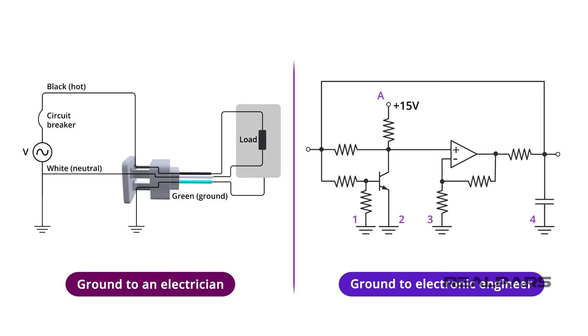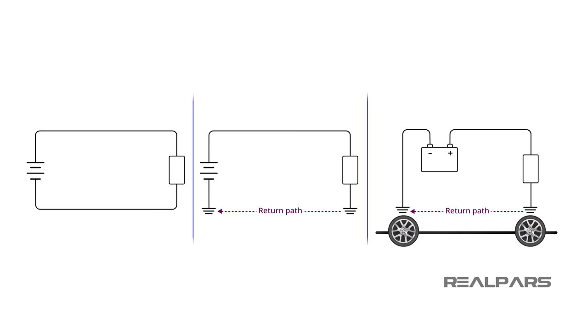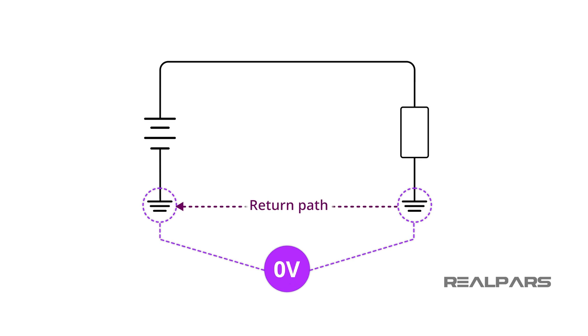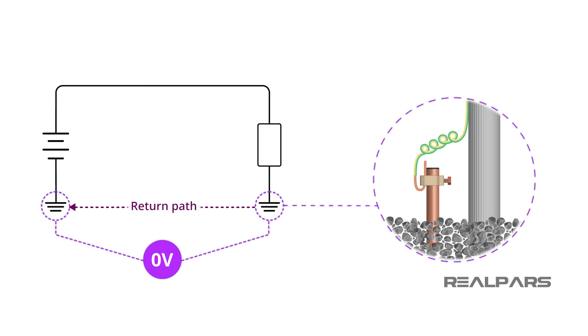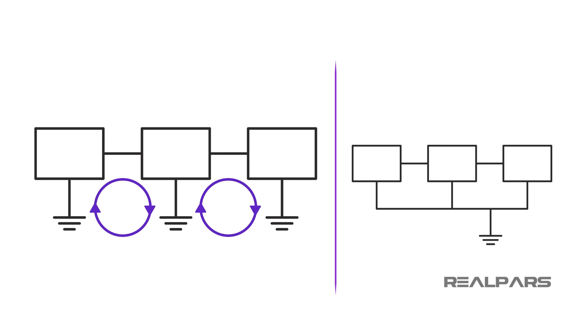Okay, let's review. Quite often, ground means different things to different people. Proper grounding is a critical safety measure in all electrical systems and installations. In many applications, grounding provides a circuit return path. Earth ground is true zero volts. It is the true zero reference for any and every electricity discussion. Earth ground is the reference point in an electrical circuit that is a direct and physical connection to the earth. A ground loop is an unwanted electrical current path that can cause havoc in equipment or process control systems by introducing unwanted electrical noise. Ground loops are created when two supposedly connected points are not at the same electrical potential.